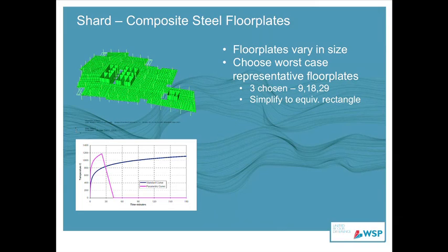So in terms of the main commercial floor plates, obviously, because the building tapers, the floor plates vary in size. But the framing on those floor plates did have some commonality in that we had double bay or single bay framing arrangements. So what we did was we agreed with the DS to model 3 representative floor plates in terms of determining the fire protection requirements.